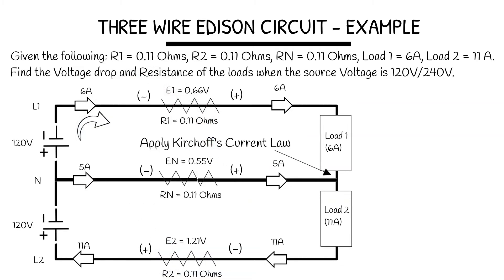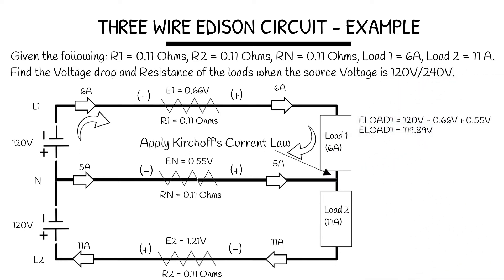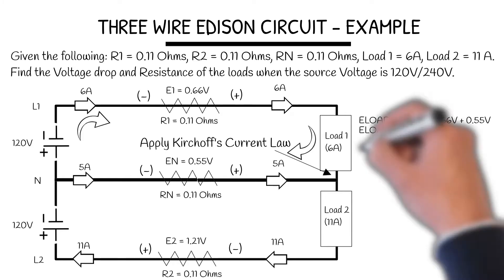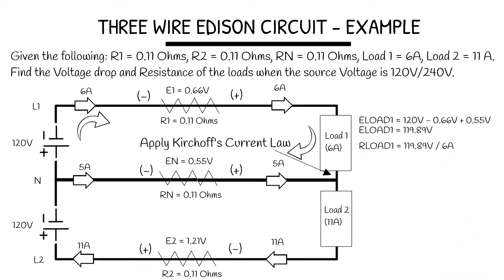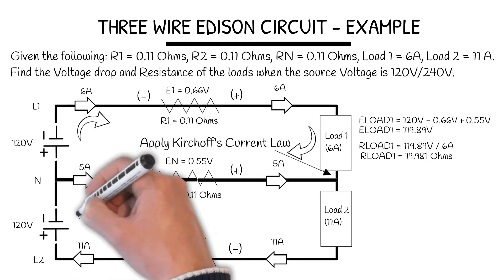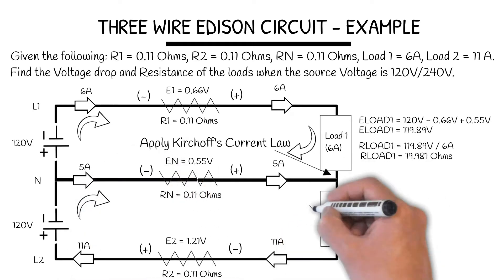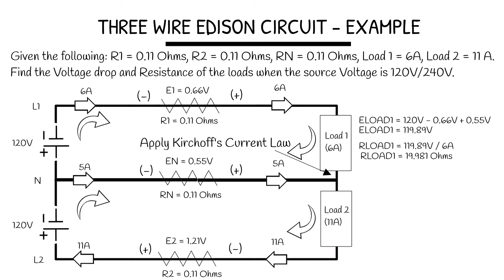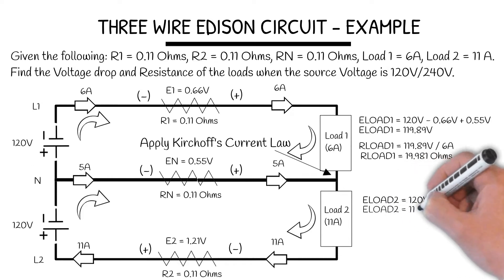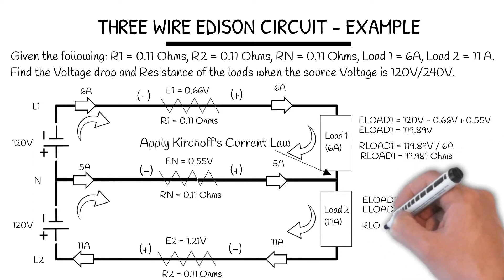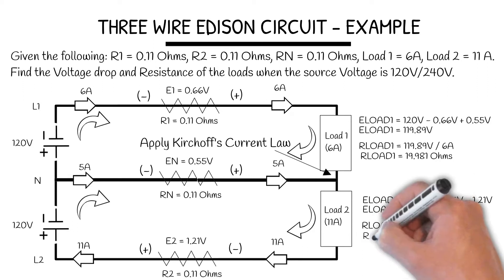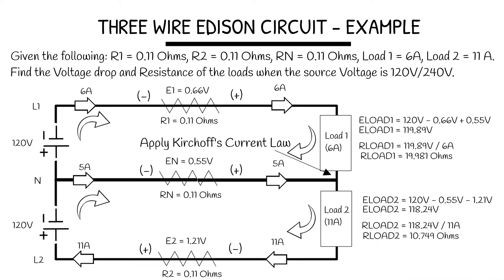To find the volt drop on load one, we must evaluate the individual loops. Taking 120 volts minus 0.66 plus 0.55, therefore load one volt drop is 119.89 volts and the resistance is 19.981 ohms. For the second volt drop, looking at the bottom loop, we have 120 volts minus 0.55 minus 1.21, which gives 118.24 volts, and load two resistance is 10.749 ohms.